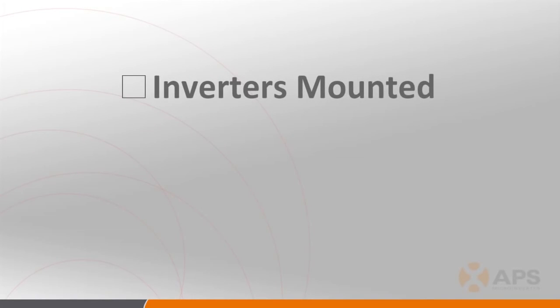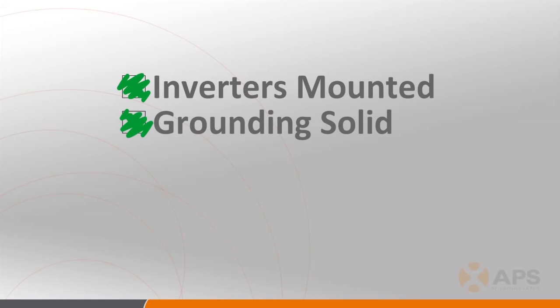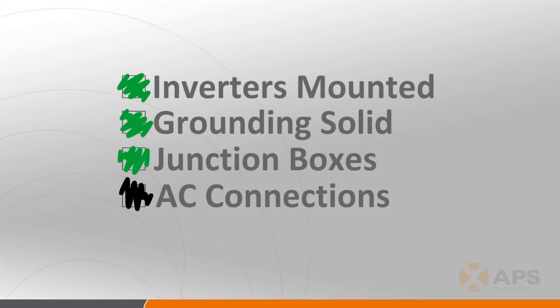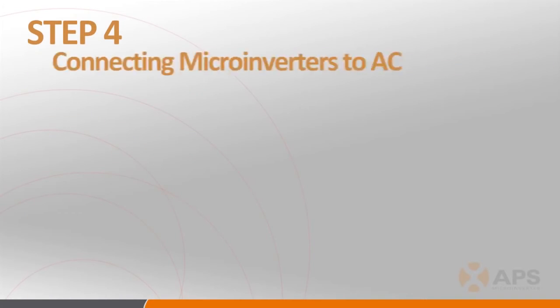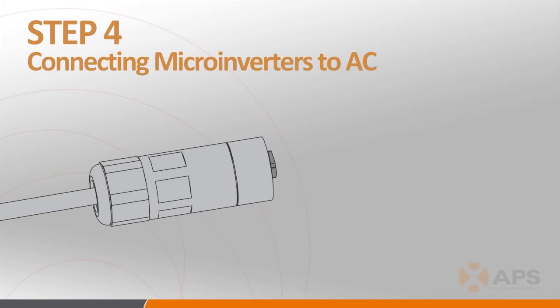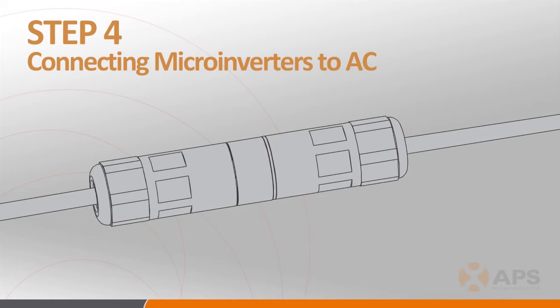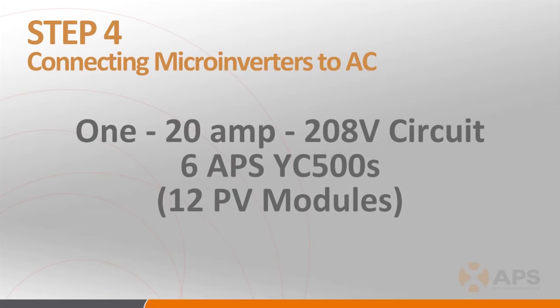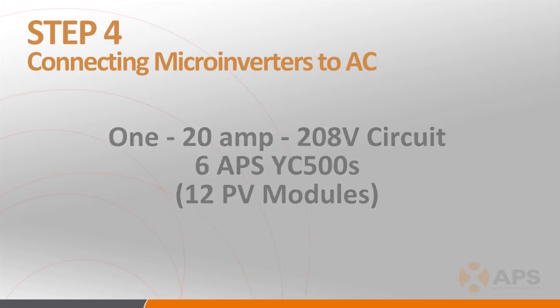With the inverters mounted on the racking system, the grounding sorted out, and junction boxes installed in the appropriate locations, it's time to connect the microinverters together on the AC side. Plug the AC female connector of the first inverter to the male connector of the next inverter, and so on, to form a continuous AC branch circuit. Remember the branch inverter limits: the maximum number of units per 120-240 volt, 20-amp circuit is 7, or a total of 14 PV modules, and the maximum number of units per a 208-volt, 20-amp circuit is 6, or a total of 12 PV modules. Do not string the AC cabling so tight that it places stress on the connection points.